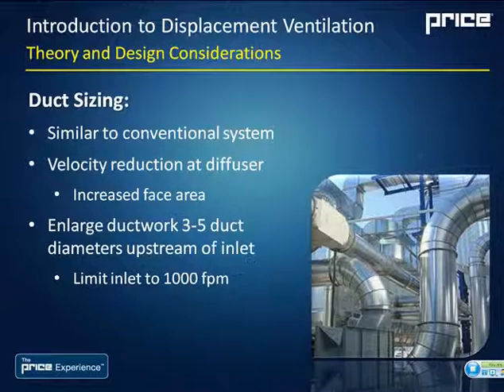Another common question is duct sizing. Because the velocity is reduced so significantly with the displacement system, a common question is whether the duct sizing has to be significantly increased, and is there a cost penalty for that? A simple answer is no. The sizing of a duct is really similar to a conventional system. Really, the majority of the equipment is very similar to a conventional system from the diffuser back. The velocity reduction is really just done at the diffuser because of an increased face area.